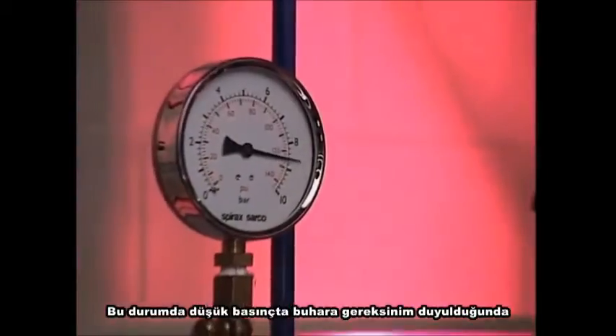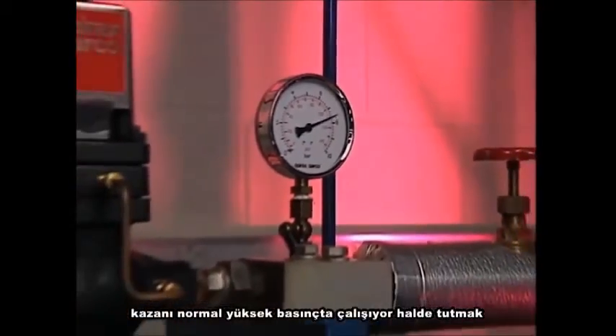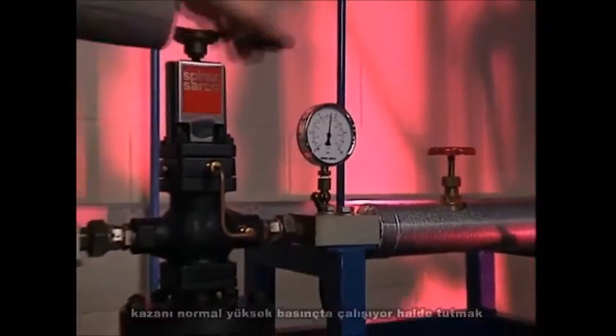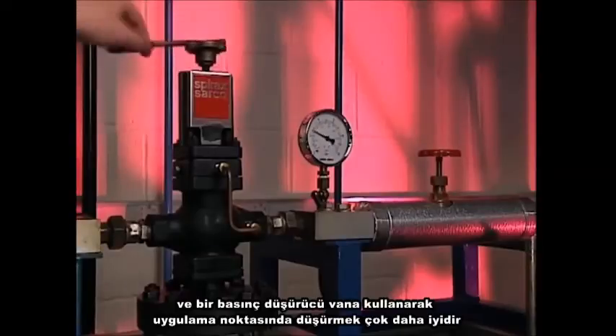So, if low-pressure steam is required, it's far better to run the boiler at normal high pressure and step it down at the point of application using a pressure-reducing valve.